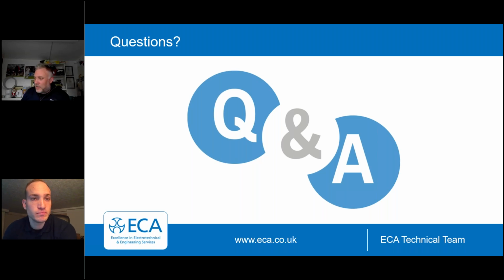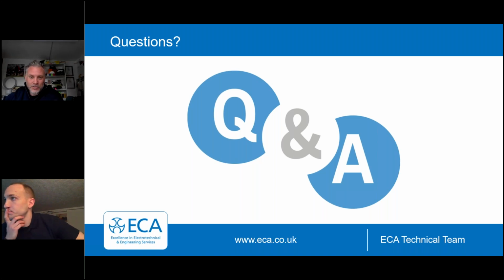You can use either. The proving unit tends to be the preferred method. In the absence of a proving unit, you may resort to a known live supply. So there's the option for both - the proving unit is the de facto first point of call, and if you can't use that, you resort to a known live supply.